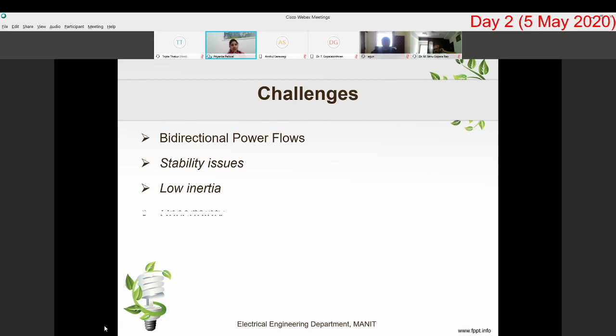Low inertia: if you look at the power system structure earlier, the generators, the synchronous machines, had very high inertia. But now you have solar PV and wind, which are connected via power electronic interfaces, and these interfaces have very low inertia. The low inertia can also be a boon, because it becomes very easy to control. But it is also a problem because they become susceptible to various transients and stability issues. Uncertainty is obviously there too, because these sources are intermittent in nature.